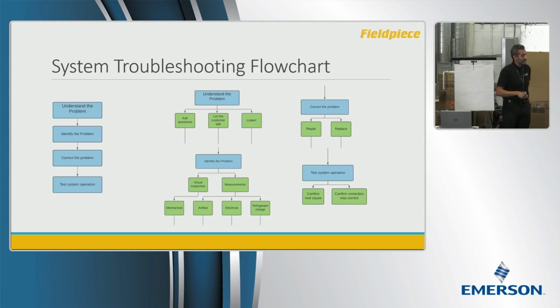Finally, and sometimes overlooked, is testing your system operation. We need to ensure and verify that the repair or replacement actually solved the root cause of the problem. Sometimes we have so many jobs in a day that this step gets overlooked because we're fairly confident we found and fixed the problem. But it's extremely important, in order to maintain a happy customer, to confirm that what you did actually worked. Using wireless technology helps us do this a lot quicker than before, so it's not something we have to skip due to time.